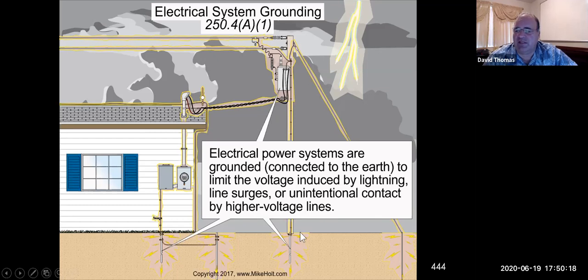So all this is saying that if we ground our system properly and we have these unwanted electrons that just pop into our system, the electrons will be able to flow to the earth through these systems of ground rods and whatever we're using to get into earth. We'll be able to use that to dissipate any of these unwanted electrons that don't belong to our system. And that's a really important point as to why we do what we do, okay? It's really about lightning, why we put the earth ground and why we tie everything to earth ground.